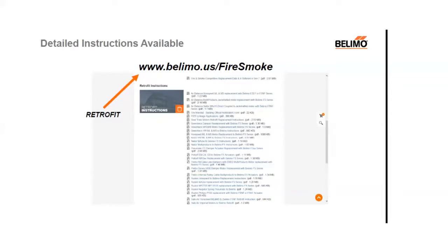If anyone is looking for instructions on replacement, at that web address there, it starts with the damper, not the actuator. But if you take a good look at all the old dampers, you'll find about 80% of them are easy to replace. They're just a coupler on a shaft. 20% of the time, you've got to do some investigation. And these instructions will show you what you've got there for a damper and then how to replace it. They're very good directions, especially when it comes to removing shaft springs and other components as you get to an internal return spring on the newer actuators.